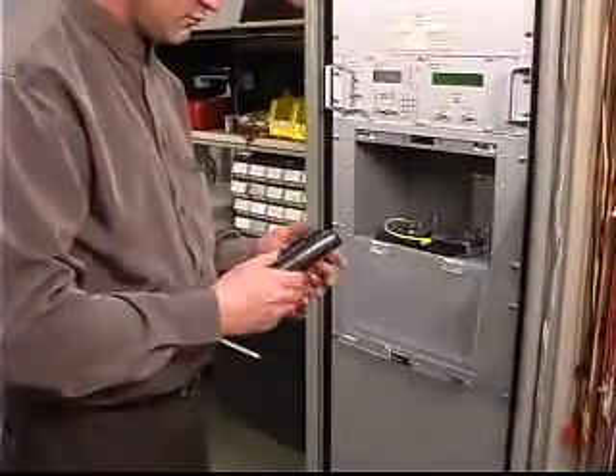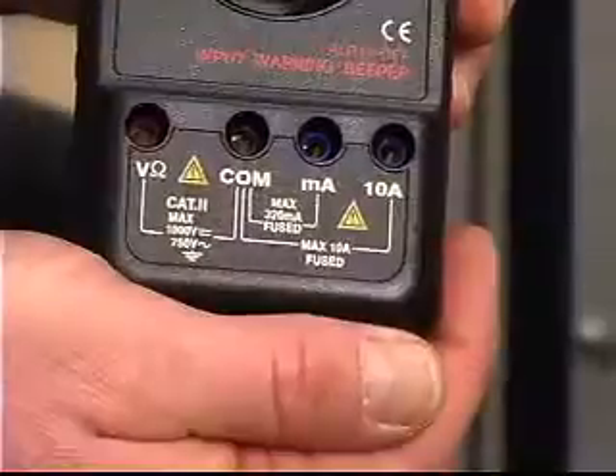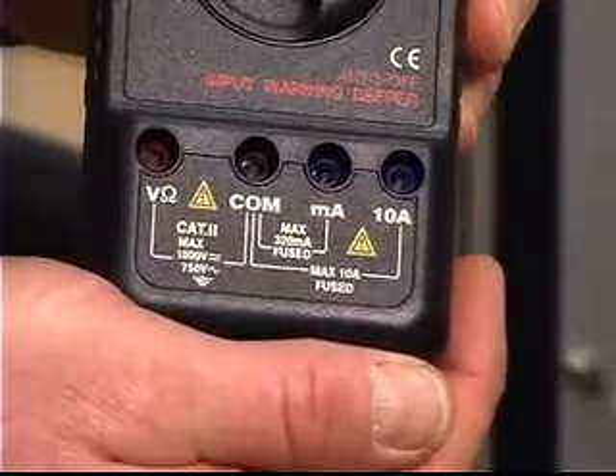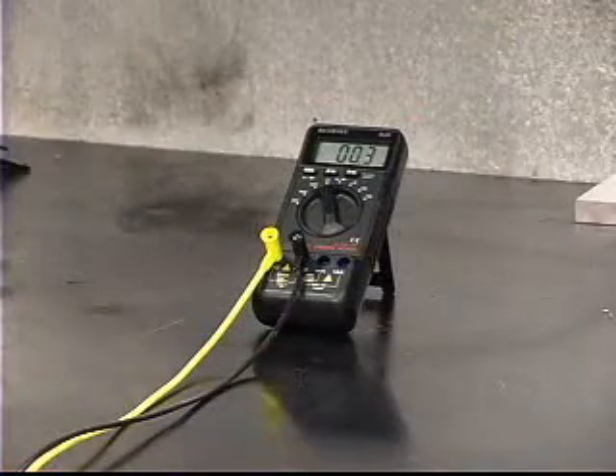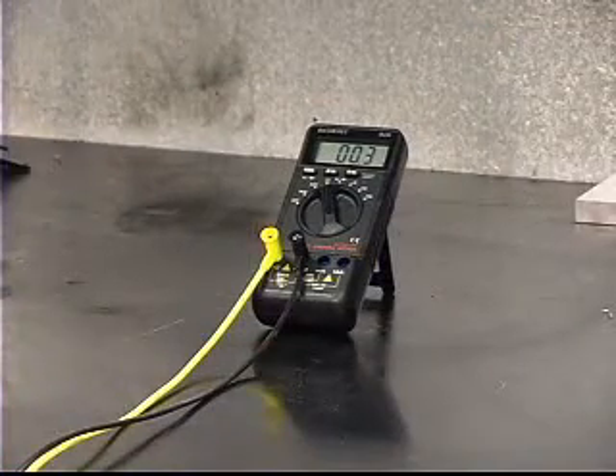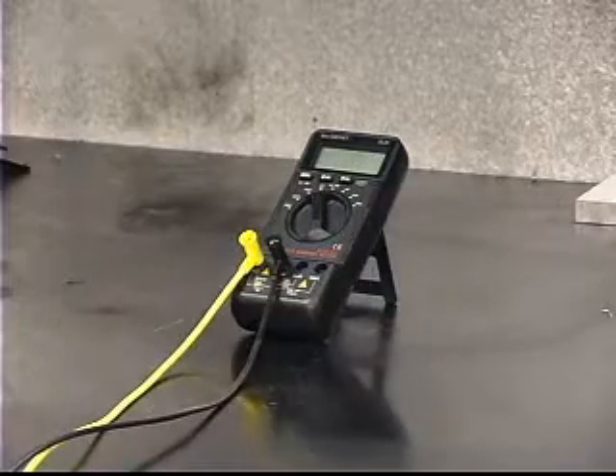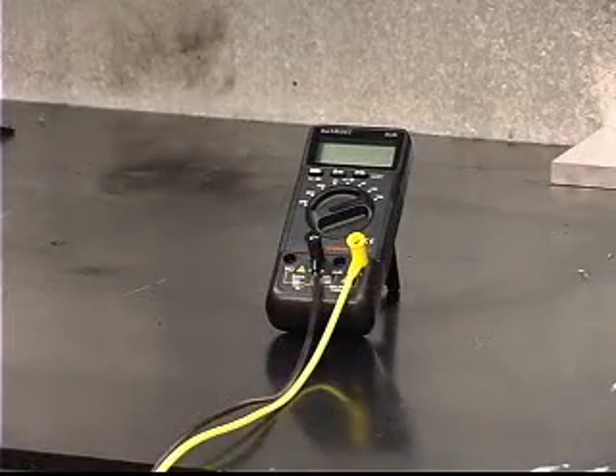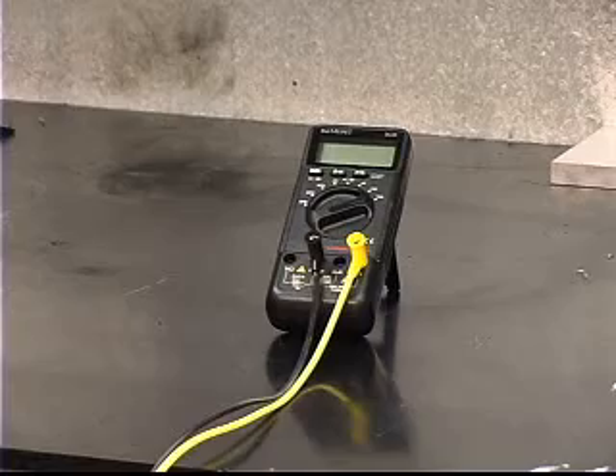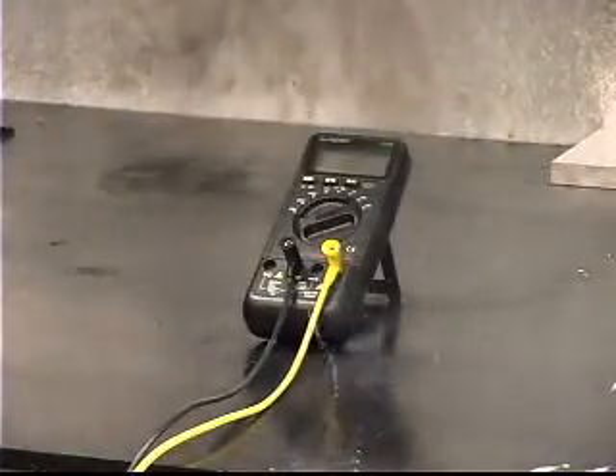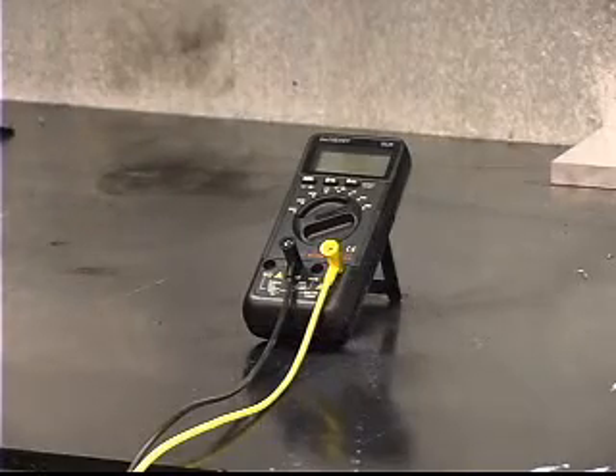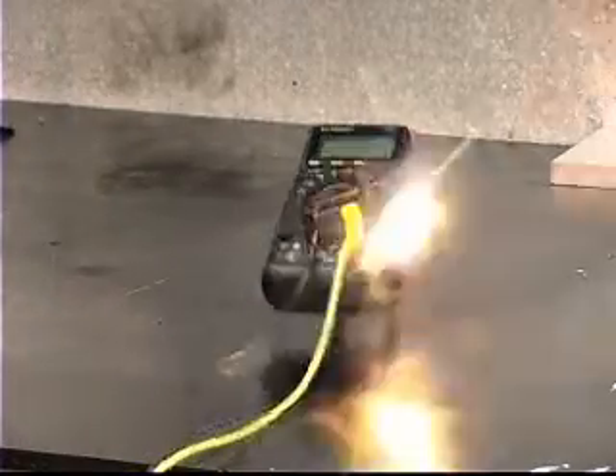This meter is marked 600 volt Cat 2. Watch what happened in this test when it was connected to a live circuit while in ohms. Here's what it does if you measure voltage using the amp's input jacks. The fuse would not protect the meter or user. Just imagine if this meter was in your hand and used on a real Cat 3 circuit.